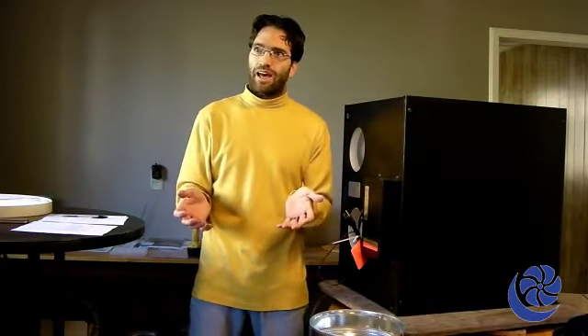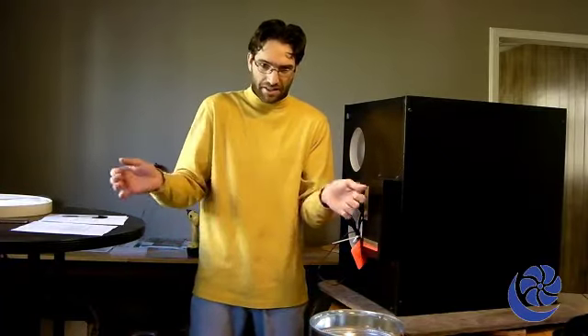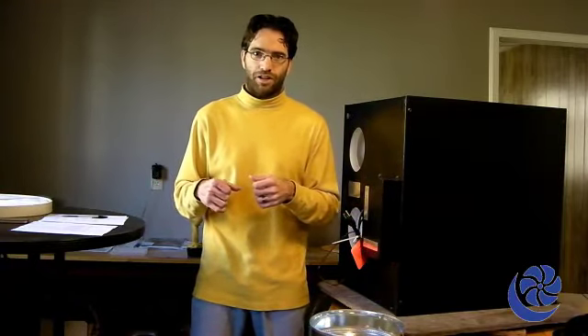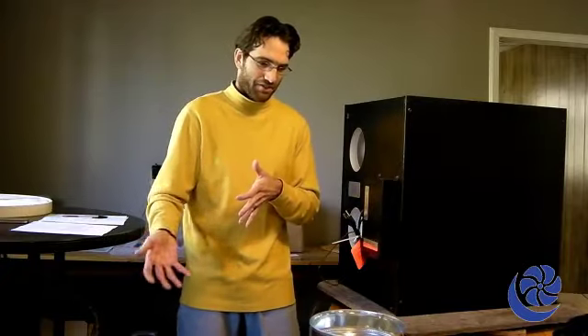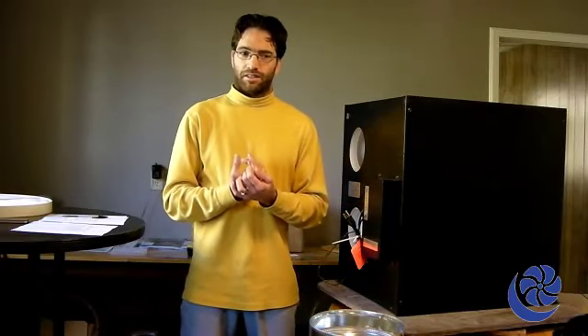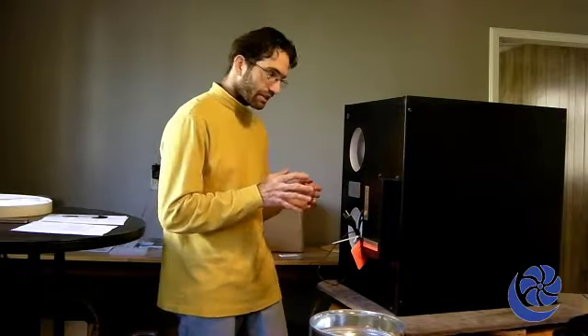You can see with that that if one airstream has a different pressure than the other, that unit is going to have to be balanced for flow because the motor has no ability to change its RPM, its control of each of the airstreams. You have to do it outside of the unit. Whereas, our unit does have independent control of each air flow, giving it constant flow capability and pressurization capabilities.